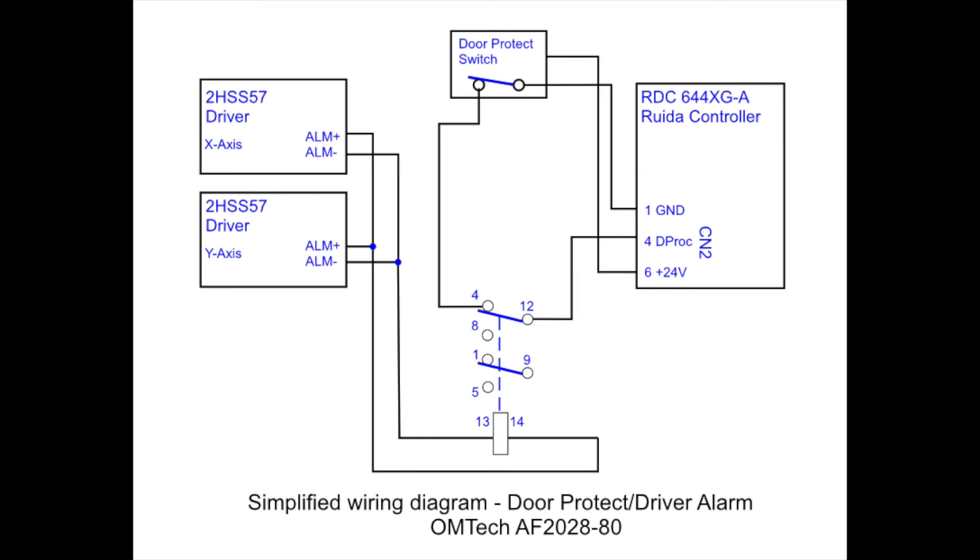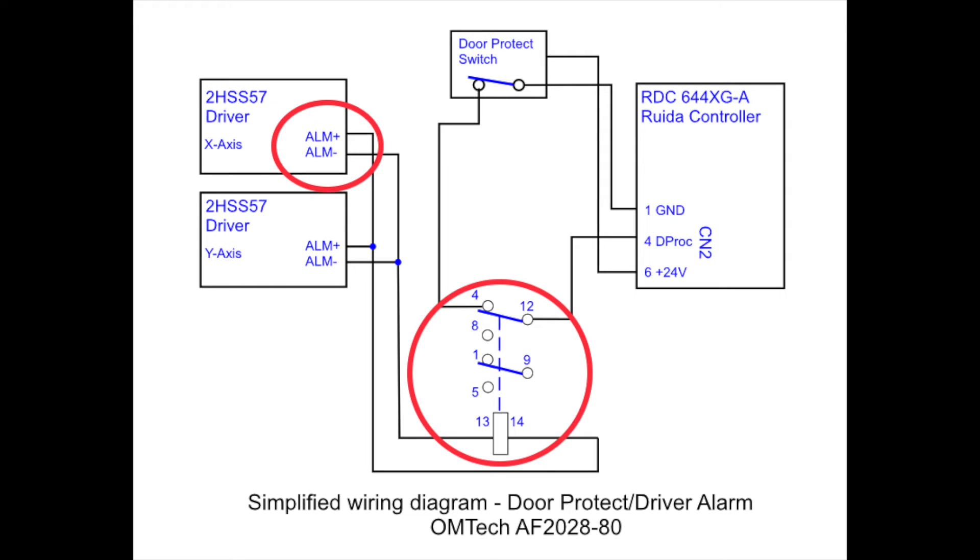Finally, here's the simplified diagram for the door protect driver alarm. To begin with, the alarm plus and the alarm negative on each of the drivers provides 24 volts out if that driver detects a problem with itself or the stepper motor loses steps. This 24 volts is fed down to the coil of the relay, which energizes it.